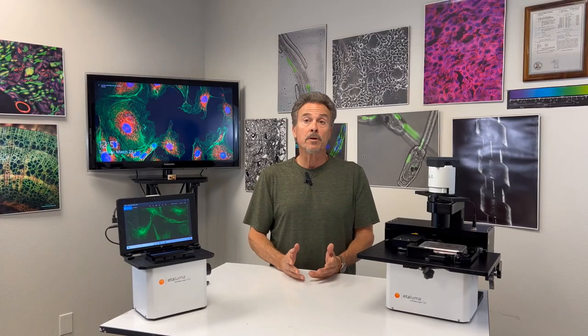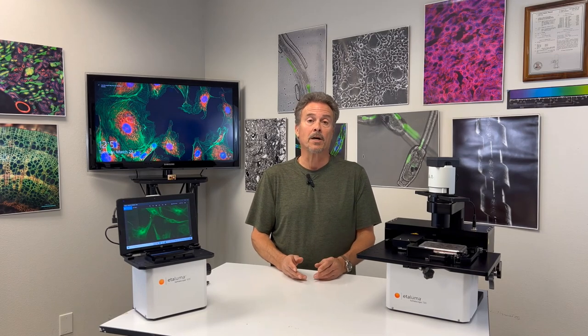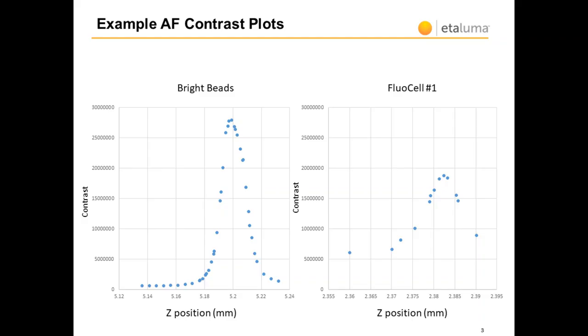It's important to understand the image characteristics that lead to reliable autofocus. Not surprisingly, this comes down to the fidelity of the contrast plot. Here are two examples of typical contrast plots for bright beads and a prepared slide in green fluorescence.